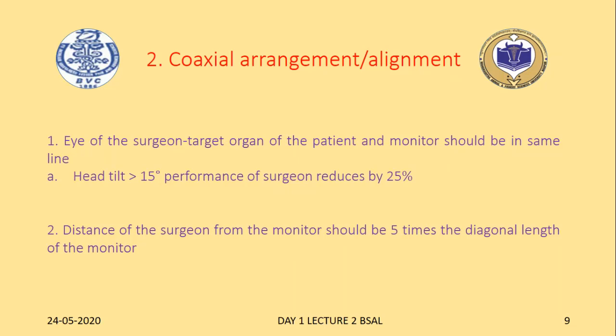Then another important thing is the level of the screen of the monitor. As I told you earlier, there has to be a coaxial arrangement. The surgeon, the patient, the organ and the monitor should be in one straight line. Now, on an average, if you sit down and just try to relax, you will realize that your eyes tend to look down most of the time. So while the monitor can be in a straight line with the eye of the surgeon, if it is 10 to 15 degrees below, it enhances your visibility.